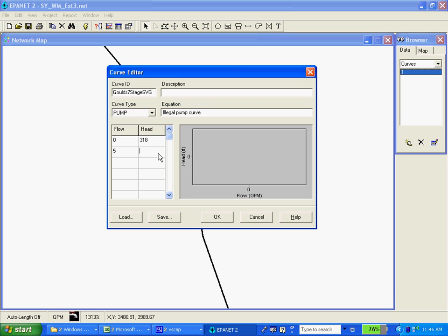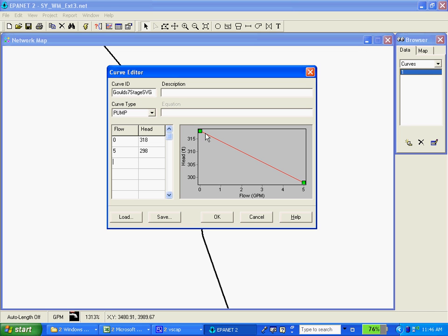You can see here the model started to try to represent a curve based on what we've entered. There are options in EPANET to do a single point and a two point curve just by entering one point of data flow versus head or two of them and they may be good options if you're just doing some preliminary modeling and you don't exactly know the pump type you're looking for. You have a general idea of what its performance needs to be. For this demonstration I'm going to actually enter in the full pump curve.